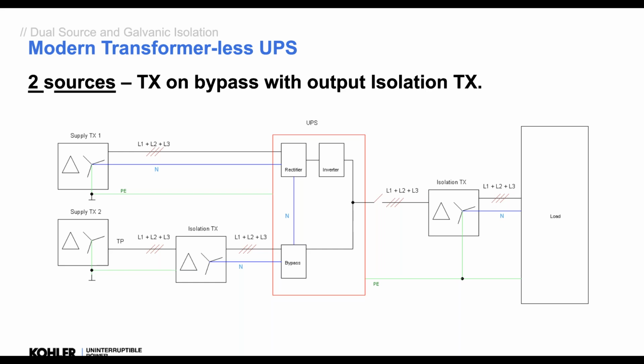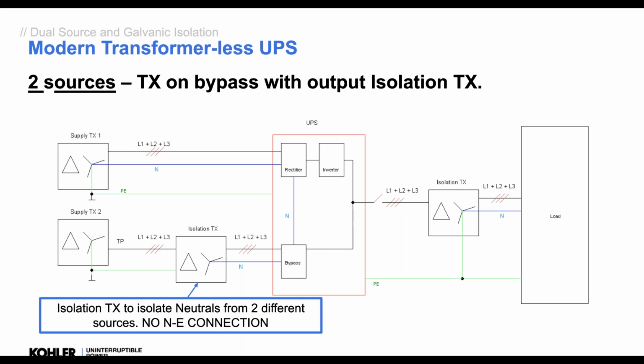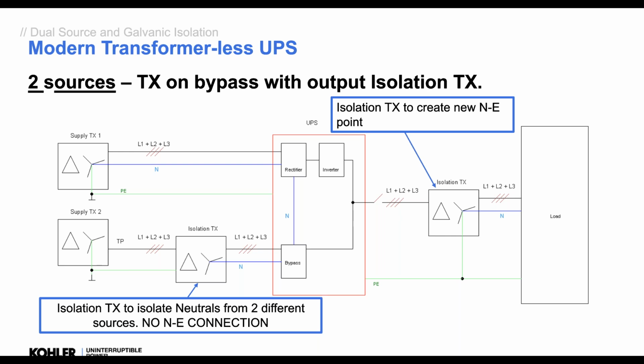On a modern transformerless UPS, which most people are using, if you want to have that UPS with two PES supplies, we have to put an isolation transformer in to separate the neutral, and we have to put an isolation transformer on the output to create a new neutral earth. Okay, that is an option, to use two PES, but what you have to think of is, do I need to put two supplies into it? Okay, because quite often these UPSs nowadays are being used as a central UPS, and we only have one supply into it. Okay, we feed the medical IT from two different UPSs. Each UPS has one supply. Okay, so that is critical to understand from day one.